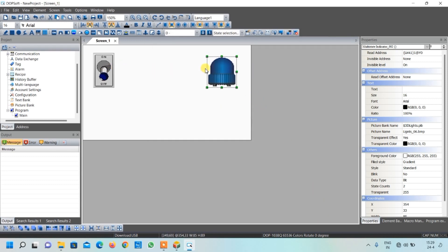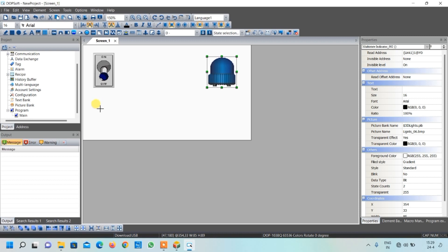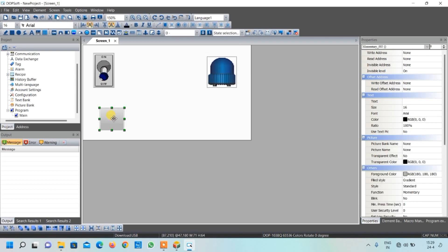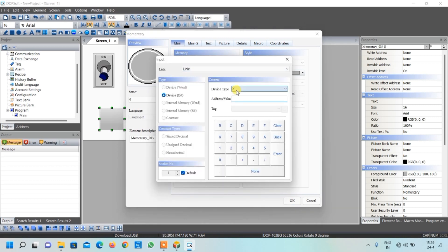Now we create the increase and decrease buttons. Go to Buttons and select 'Momentary' since we just want a pulse input. Draw a box, then double-click it. From Style, change it to Round so the buttons will be round. Write the address - the increase button is X1 in the hardware connection, so write X1 and press Enter.